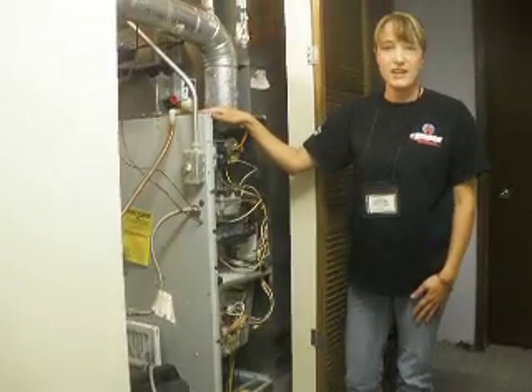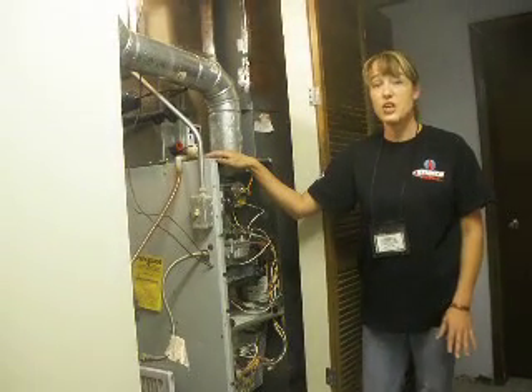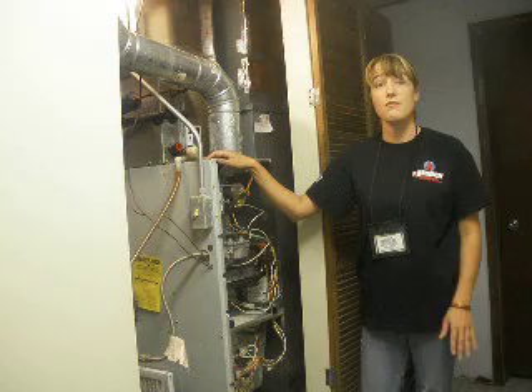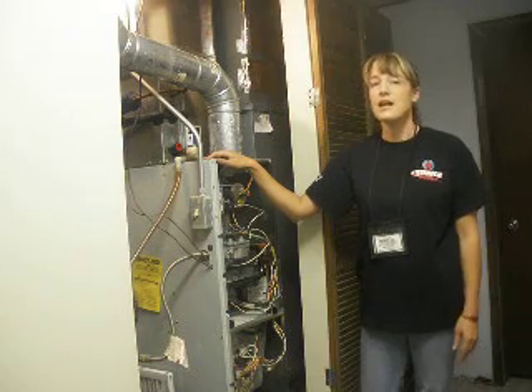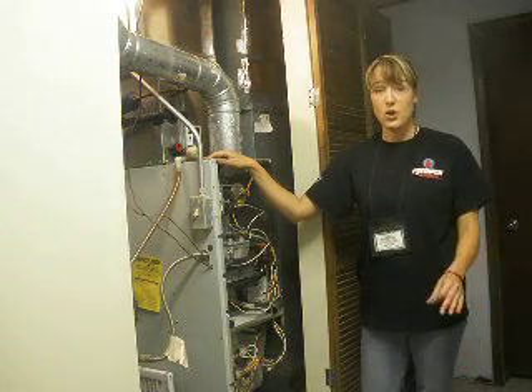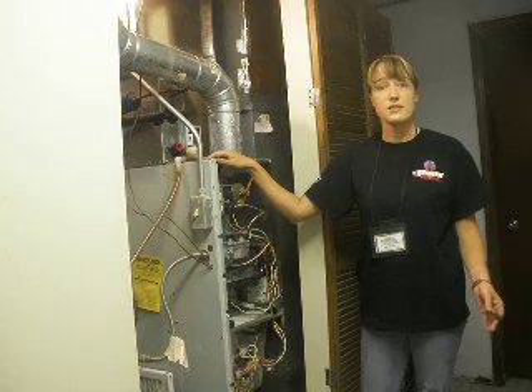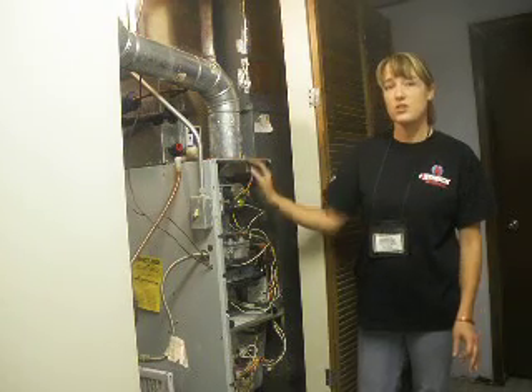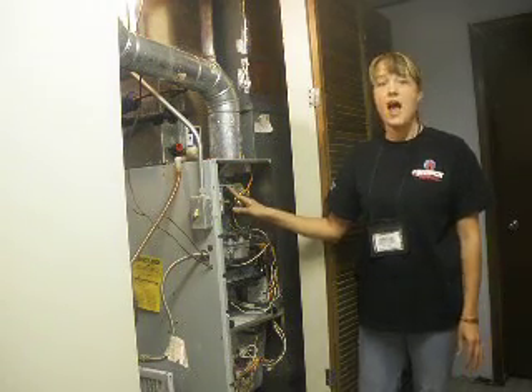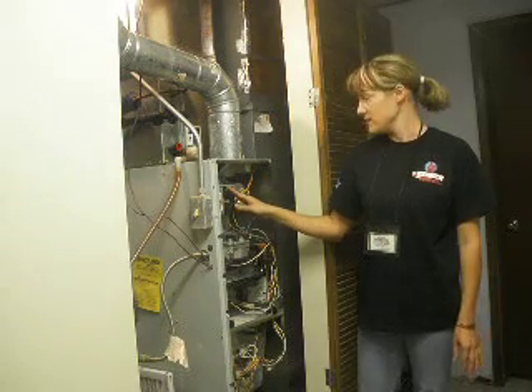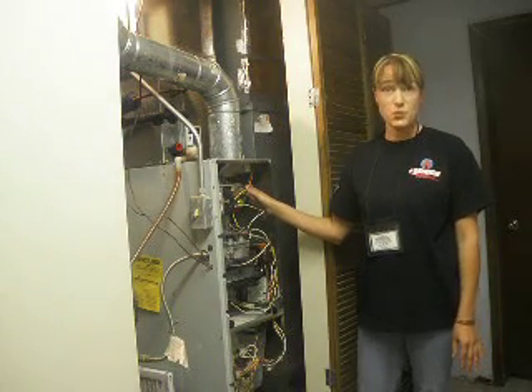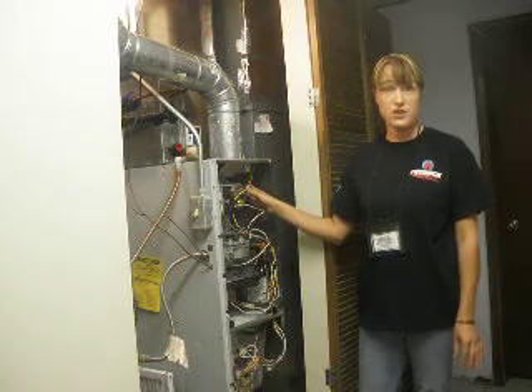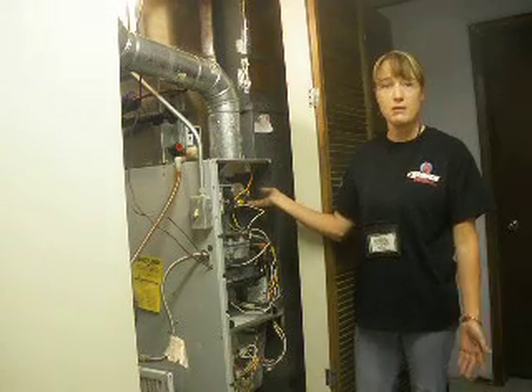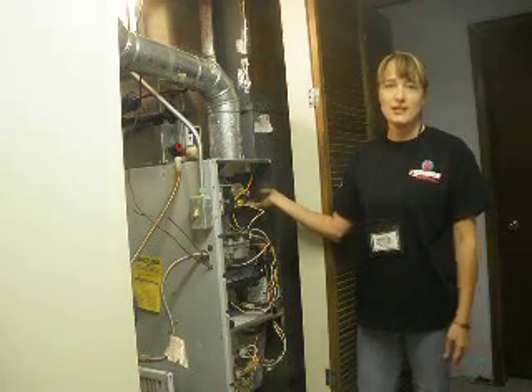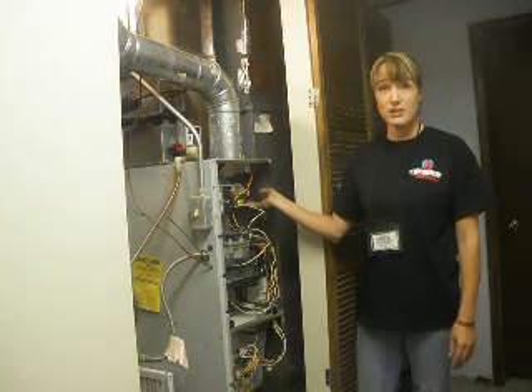We have an 80% gas-efficient furnace today. Generally, this type of furnace has a sequence of events during the heat cycle. It starts by you being cold, going to the thermostat, and raising the set temperature. That signals the furnace to start the draft inducer. And almost instantaneously, the pressure switch recognizes the draft inducer is functioning. There's a port here that can sometimes get clogged, which I can correct easily during the cleaning and inspection.